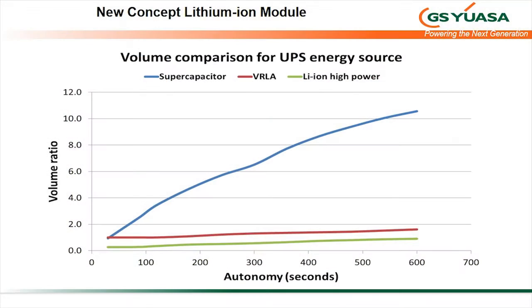If you look at the volumes comparison as well, it's not such a stark difference in volume terms, but still you're looking down at that 30 seconds area of two or three times, up to four times less volume occupied by lithium ion compared with lead acid or compared with supercaps in this case. So there is a volume saving as well. And because of the weight, with lead acid you can't go to very high racks, not really going much above that level. Whereas with lithium ion, you can easily go much higher, while still maintaining a good floor loading. So that means the footprint can be very significantly improved. So big difference in volume comparison as well.